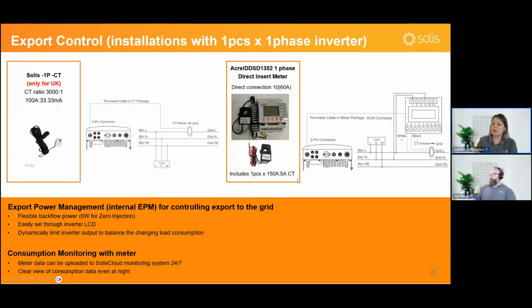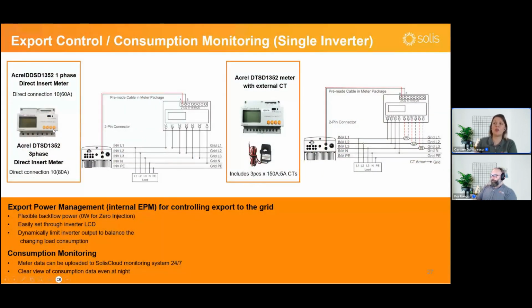So these can be either single phase or three phase meters. They can have direct connections, or they can have CT clamps. The CT clamps they come with can measure up to 150 amps, and they have a 5 amp secondary current. The direct connection meters have a limitation because they can only measure up to 80 amps. So if you are using them in installations where the current flowing through the grid connection point is higher than 80 amps, I would recommend using the meter type with external CTs, because it will allow higher current.